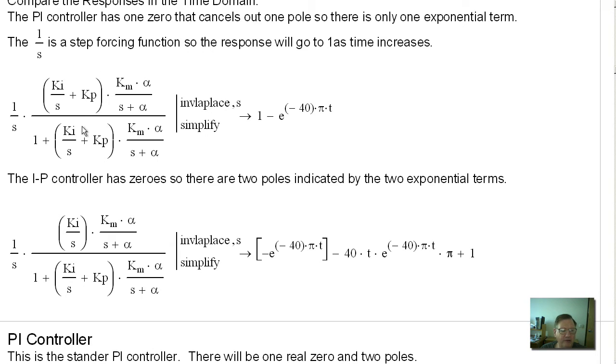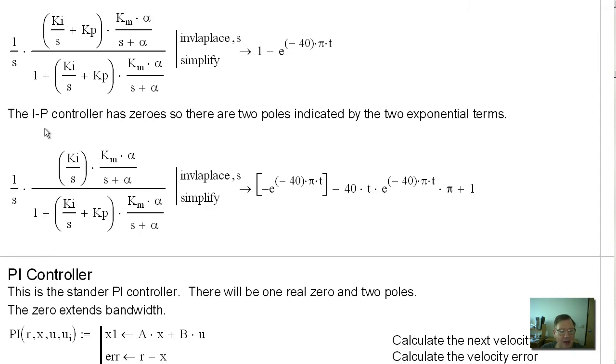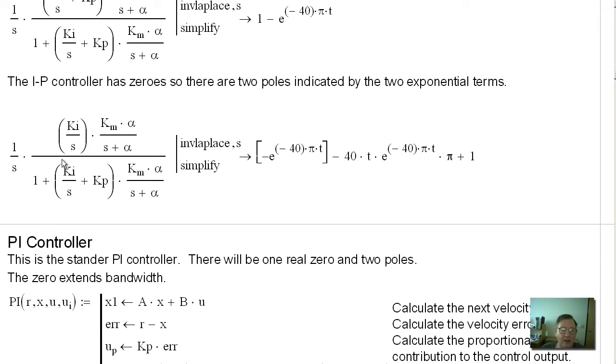So what this means is the integrator gain and the proportional gain act on the difference between the target and the feedback, or the set point and the process variable if you're a process guy. In this case, only the integrator gain is acting on the error between the target velocity and the actual velocity, and the proportional gain is only acting on changes in the actual velocity.